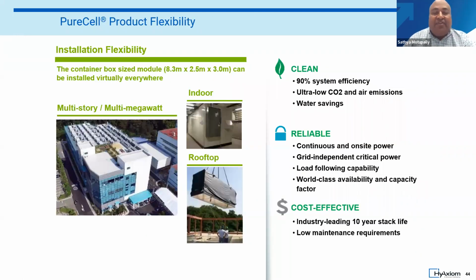The benefits of stationary fuel cells, and the HyAxiom fuel cell in particular, start with very high system efficiency. Because we utilize 90% of the heating value of the hydrocarbon fuel, we have very low CO2, NOx, and SOx emissions—in fact, almost zero NOx and SOx. The fuel cells can also run in water balance for the majority of conditions, so there's really no impact on water uptake.